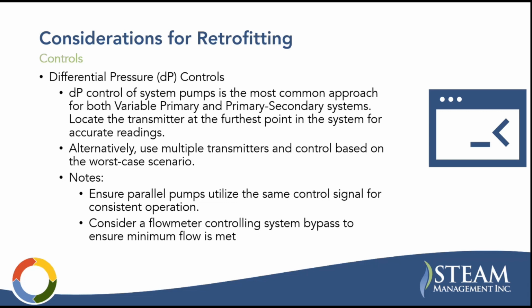And then there's another question that says, what would be the benefit to changing out the endpoint heat exchangers, like fin tubes, to permit much lower water temperatures down to near 100 Fahrenheit? And what are the anticipated financial barriers to this as an option? Yeah, that's a great question. So if you can change out your terminal units to A, operate at a lower supply temperature, and B, have a higher delta T across them to minimize the return temperature, that will help minimize that overall return temperature back to the boiler and promote being able to operate in condensing mode.